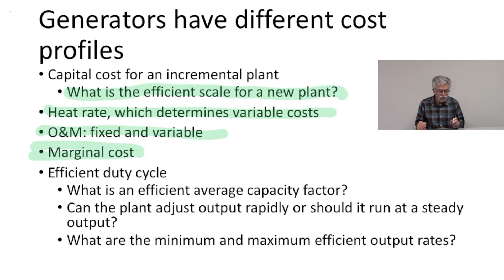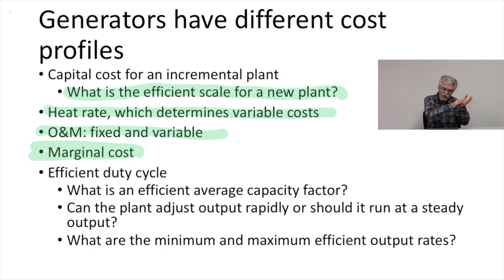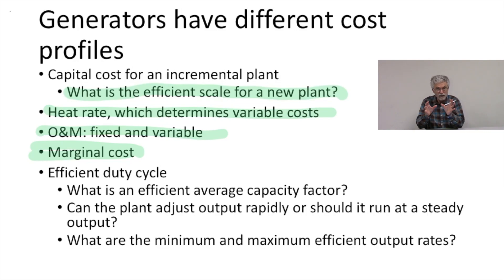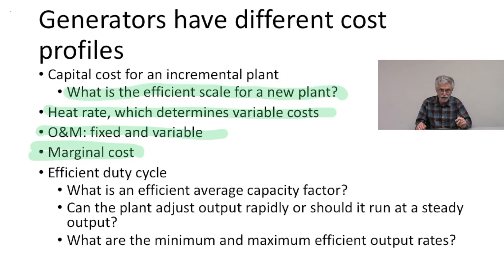We want to know what the marginal cost of generation is. The marginal cost of generating with a given power plant is going to change depending on whether we're running it at a very low capacity factor, or at its engineering target capacity factor where it'll probably have its lowest heat rate, or at a very high capacity factor where the heat rate will tend to go back up again. For the purposes of our simple examples, we're going to generally assume that the heat rate is constant.